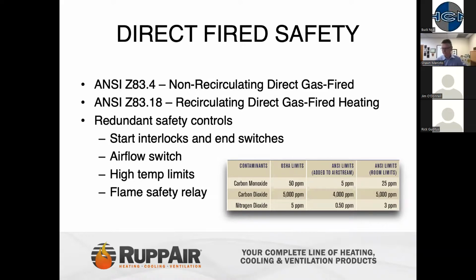Okay, last question. Does Rupp recommend high temperature air supply at 140 degrees Fahrenheit or above? It doesn't make sense to me. The air is hot enough to burn people or products. Hot air rises in these spaces, and they can be 40 feet high. In addition, you have to coordinate the high temperature supplies of 160 degrees with the fire alarm/sprinkler system that has a standard trip setting at 165 degrees.